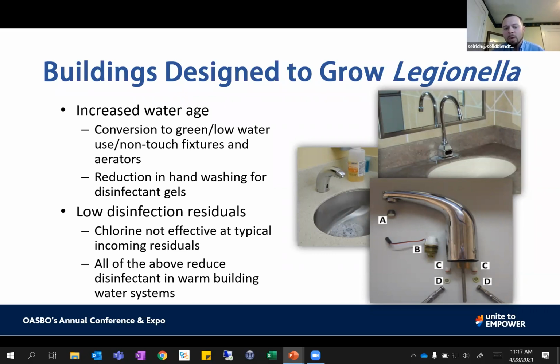When you get into warm water, that water is typically going to be a recirculating loop. As that water is circulating throughout the building, the heat is literally driving the chlorine out of the water. So again, you've got the warm temp that's perfect, and you've got no disinfectant in the system.